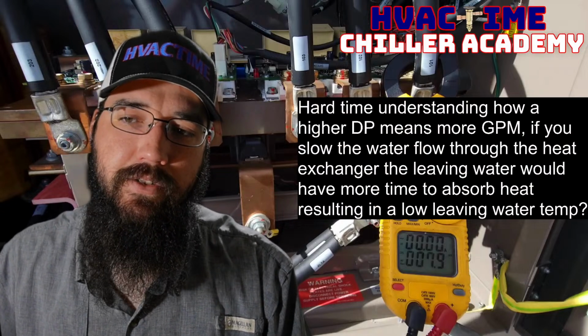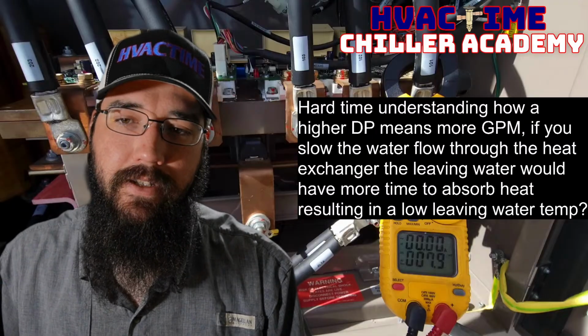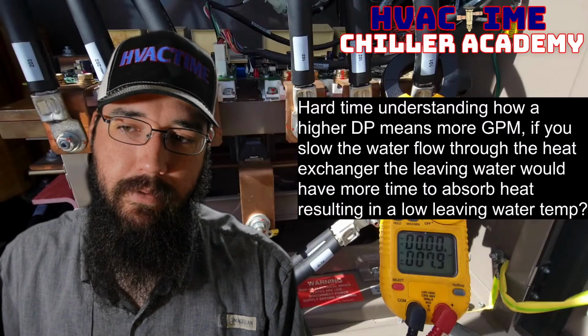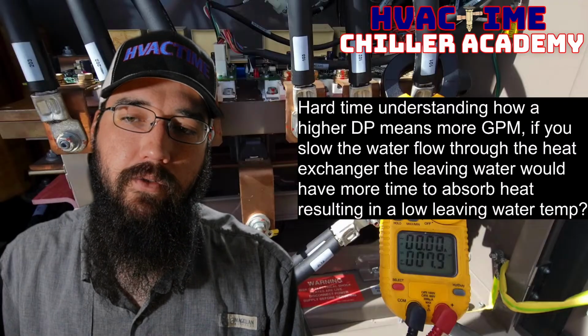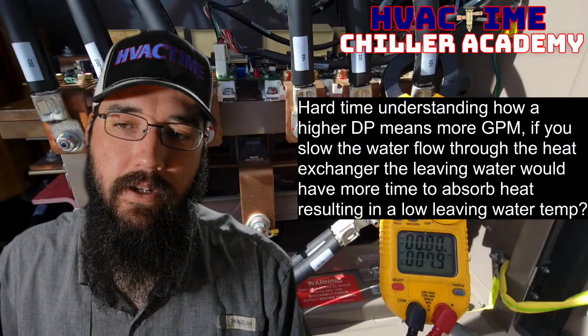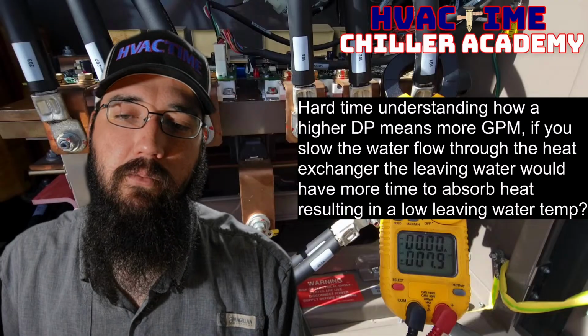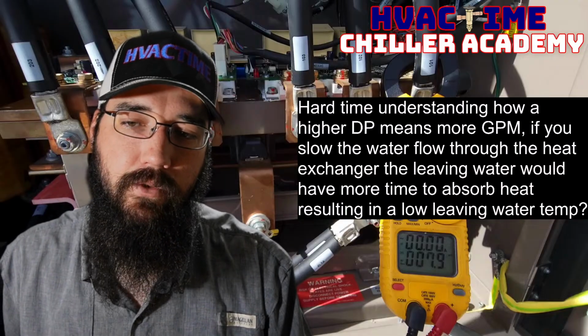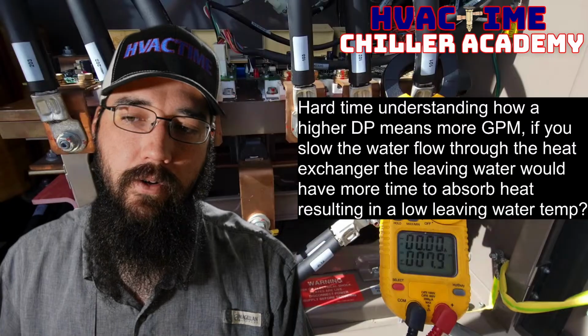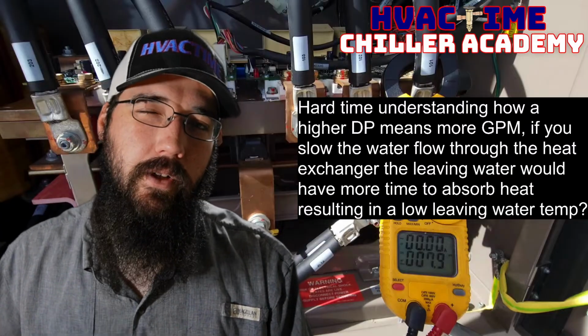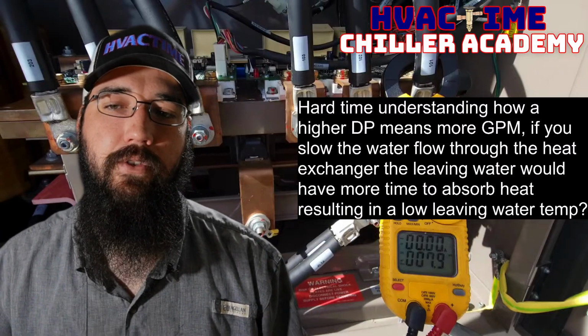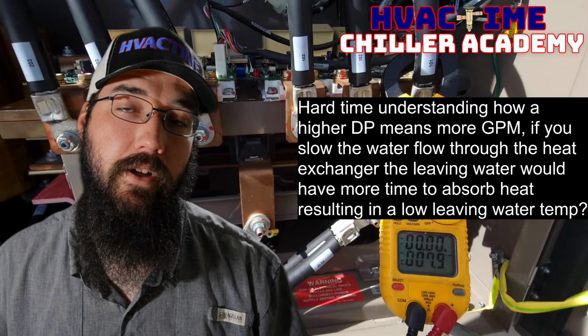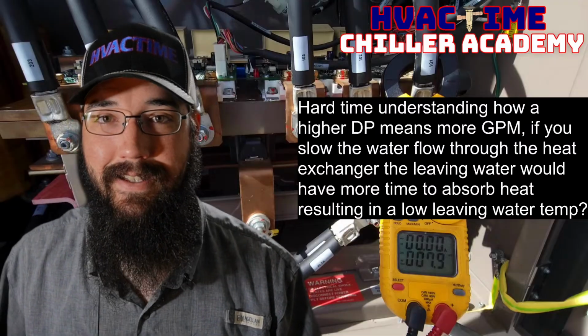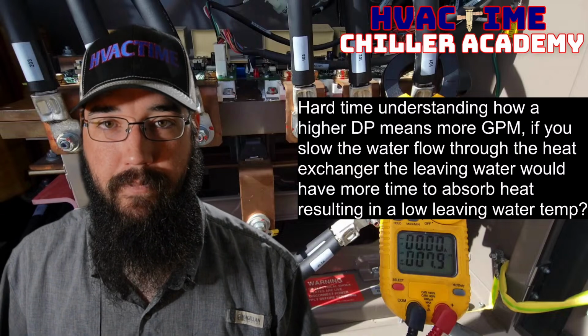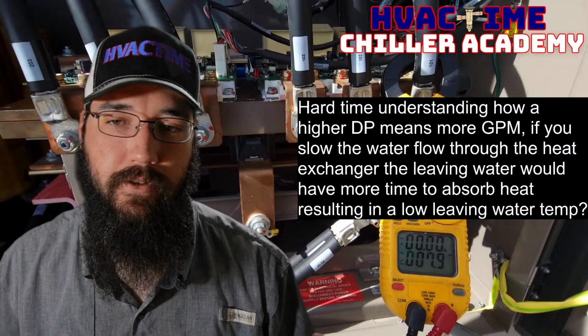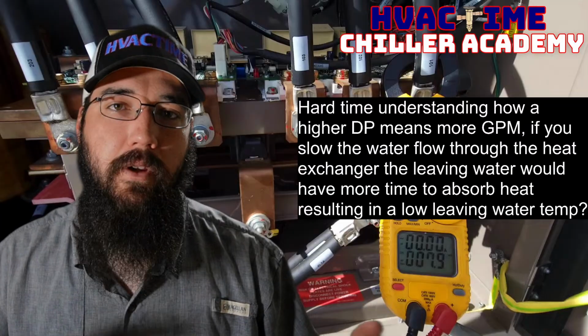Hard time understanding how a higher DP means more GPM. If you slow the water flow through the heat exchanger, the leaving water would have more time to absorb heat, resulting in a lower leaving water temperature. So we do have to be careful that we're not confusing DP for differential pressure and TD for differential temperature, okay, or temperature differential, pressure differential. Be cautious of that, all right?